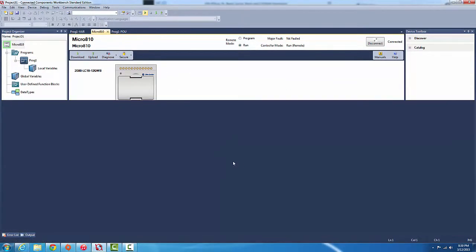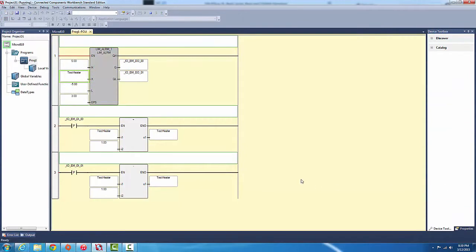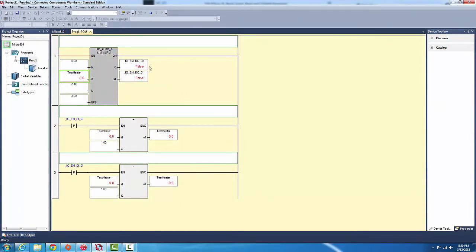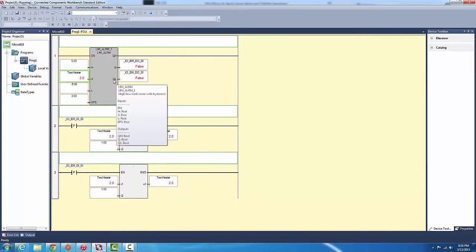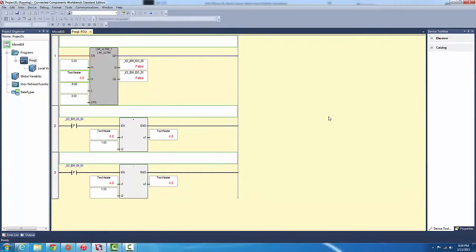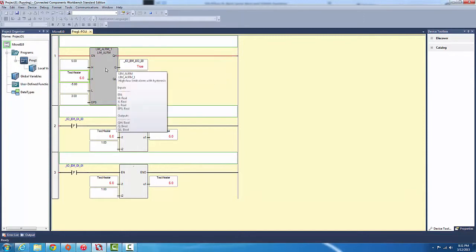So let's see this baby at work. Press play. As we can see here, test_heater has zero. Both outputs on this limit alarm block is false, and we got our addition and subtraction. Let's start adding. One, two, three, four, five. When we go six, it's gonna go true and it's gonna close.